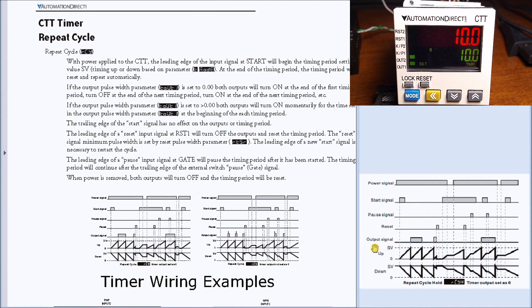If we have the output signal on continuously, that being that it's set for 0.00 seconds, what will happen is the output itself will cycle on for the time duration and then off for the time duration and on for the time duration. So it's a cycle, a repeat cycle.